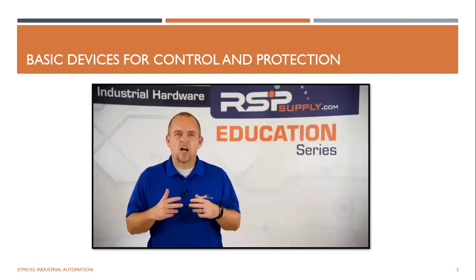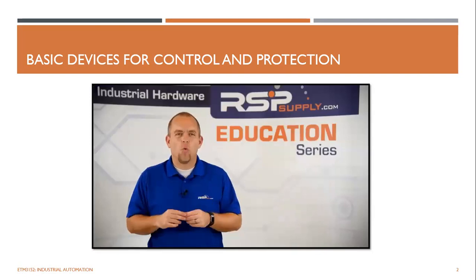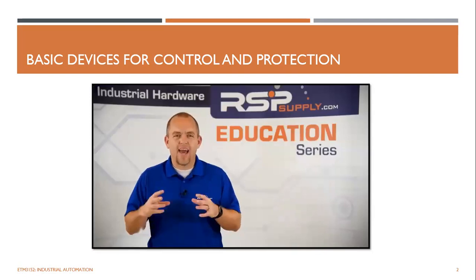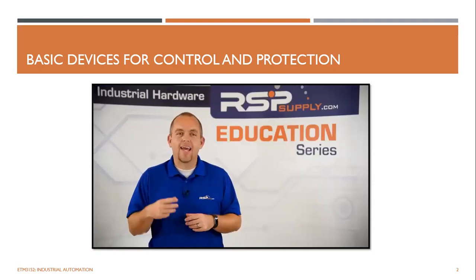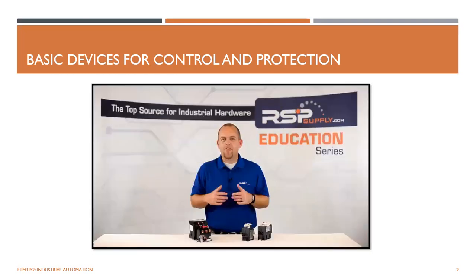Next, let's talk about overload protection. An overload is designed to protect the motor against a prolonged overcurrent. What this means is if the motor is running at too high of a current for too long, it can overheat and destroy the motor. How the overload provides this protection is it has a current sensing unit built within the overload itself. We have either an electronic current sensing unit or a thermal current sensing unit, depending on the type of overload that we use.